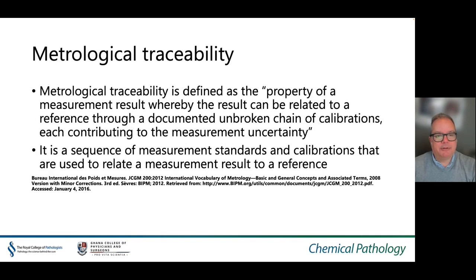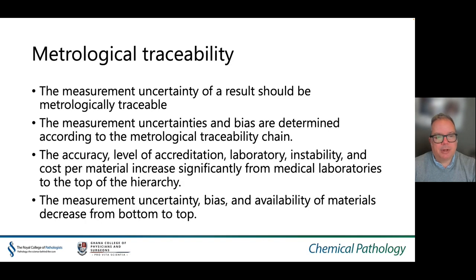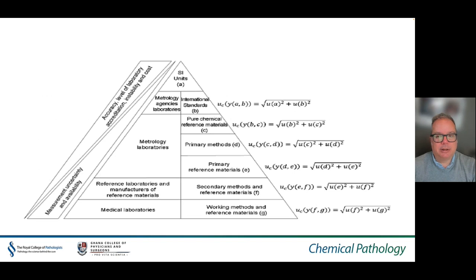Metrological traceability is defined as the property of a measurement result whereby the result can be related to a reference via a documented unbroken chain of calibrations, each contributing to the measurement uncertainty. It is the sequence of measurement standards and calibrations used to relate a measurement result to a reference. The measurement uncertainty of a result should therefore be metrologically traceable. The accuracy, level of accreditation, laboratory instability, and cost per material increase significantly from medical laboratories to the top of the hierarchy, while measurement uncertainty, bias, and available materials decrease from bottom to top, as illustrated in the diagram.